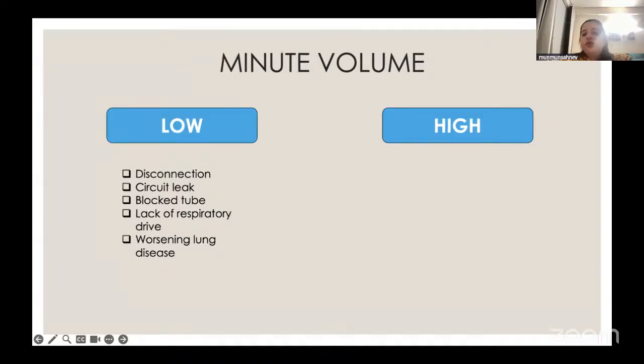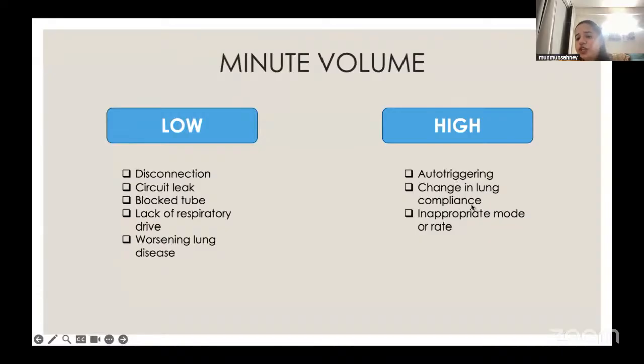Similarly, a high minute volume indicates that too much tidal volume or too high a rate is being used by the baby. So this indicates that there has been some sort of overventilation, leading to hypocarbia. A high minute volume alarm may indicate that there is some auto-triggering. Auto-triggering could be because of leaks around the ET tube or the water which is in the circuit. It could also happen when there has been a rapid change in lung compliance.